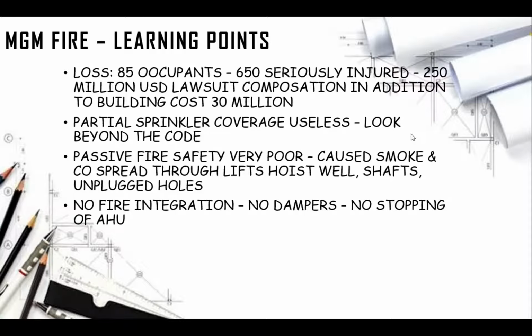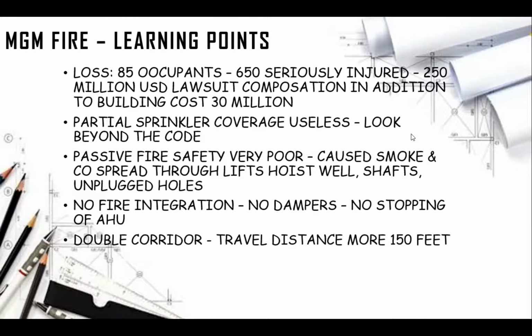So when the fire alarm starts, the integration should work: the lift must come down to the ground floor, and the AHU must be stopped automatically. Smoke exhaust in the basement should start. So these are all the fire integration systems, what should be on and what should be off. But that's not what happened in that MGM fire. So that is the main reason it killed many. And there was a double corridor, with travel distance of more than 150 feet. This is also too high. The travel distance, number of means of exit, location of exit, and width of the staircase are all very pertinent and very important from the fire safety point of view. In addition to that, fire resistance rating and fire compartments were not there. That is a main flaw.